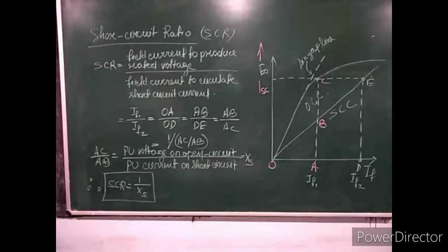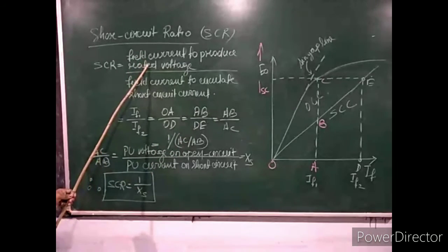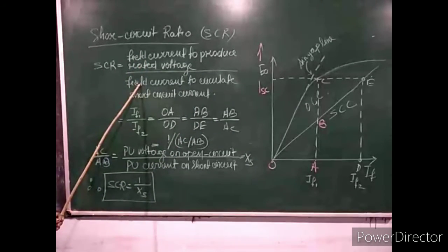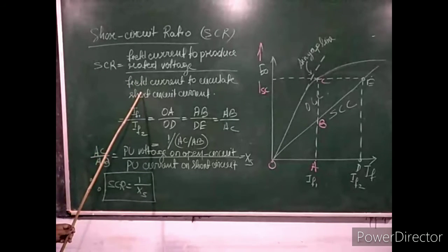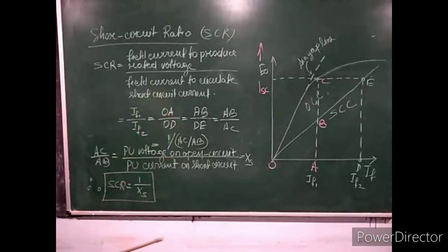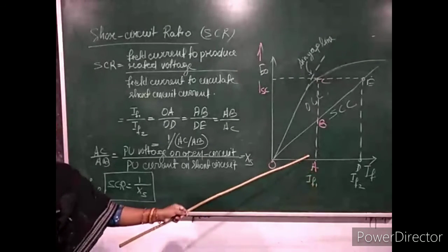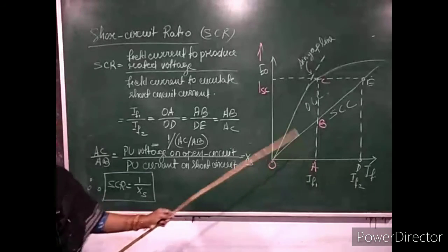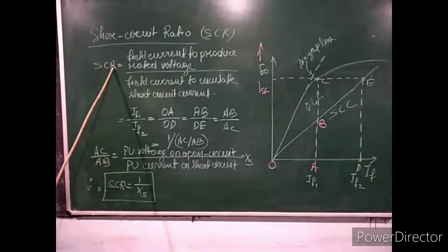The next point is short circuit ratio. What is short circuit ratio? Short circuit ratio is defined as the ratio of the field current to produce rated voltage to the field current to produce the rated value of short circuit current when the alternator runs at synchronous speed. From this graph, you will calculate the short circuit ratio.